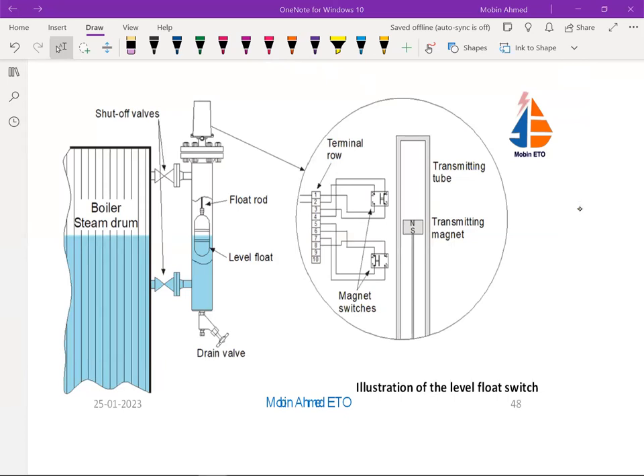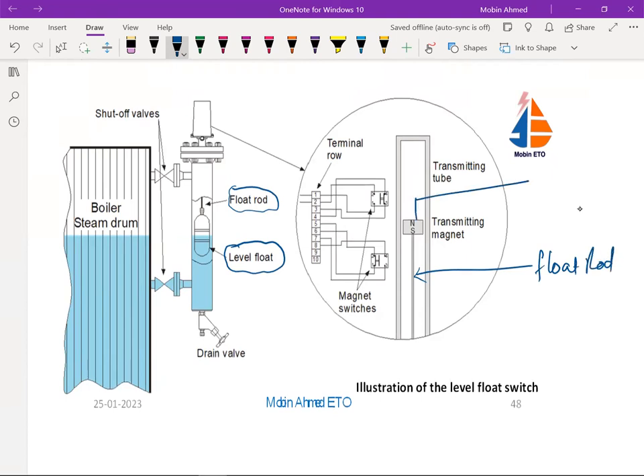Now here you can see this is a float, level float. This one is a level float. And here there is a float rod. So this connecting rod or float rod. And this one again, this is a float rod. And this one is a magnet. So with the level float rod and the magnet that is connected together in a transmitting tube. So this is a transmitting tube where it is being connected. Then we are going to have a magnetic switch. Two magnetic switches are there.